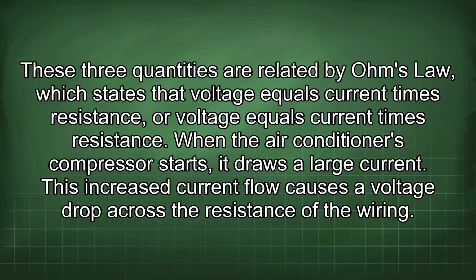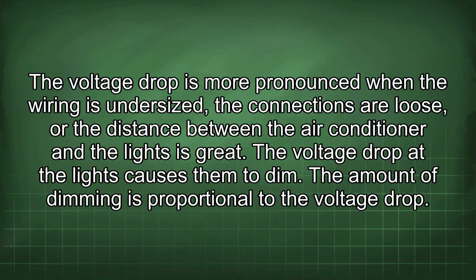When the air conditioner's compressor starts, it draws a large current. This increased current flow causes a voltage drop across the resistance at the wiring. The voltage drop is more pronounced when the wiring is undersized, the connections are loose, or the distance between the air conditioner and the lights is great. Voltage drop at the lights causes them to dim. The amount of dimming is proportional to the voltage drop.